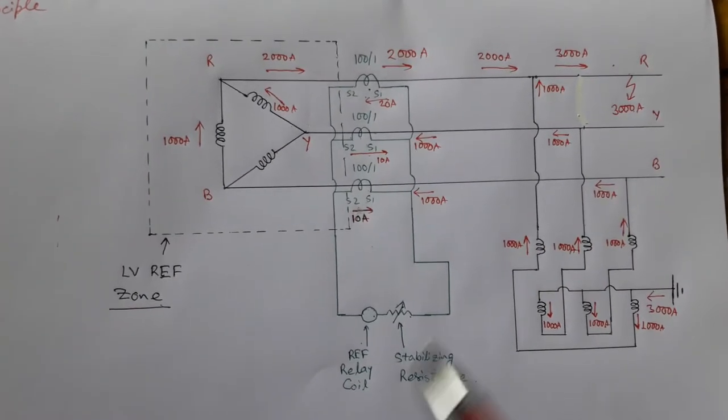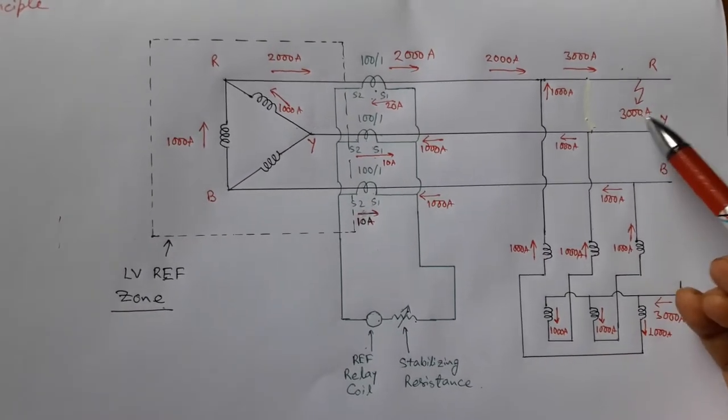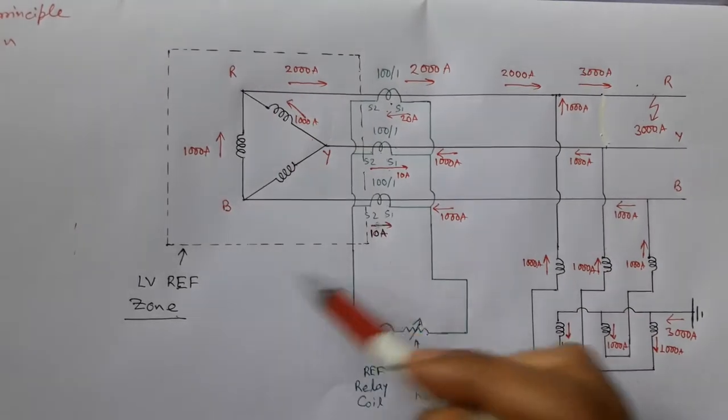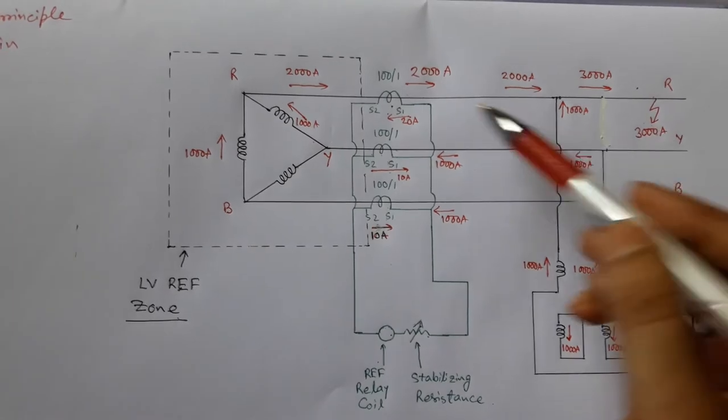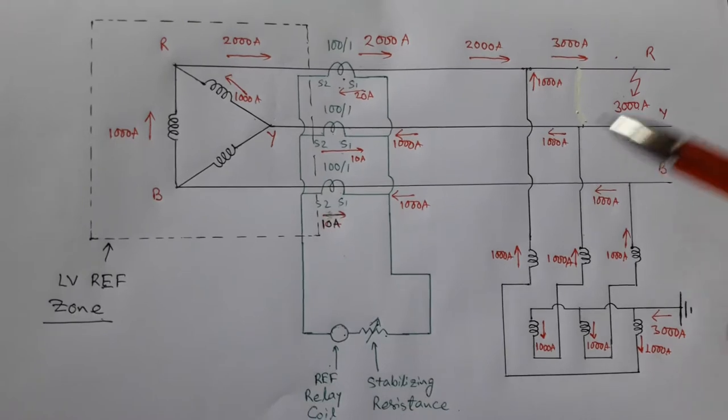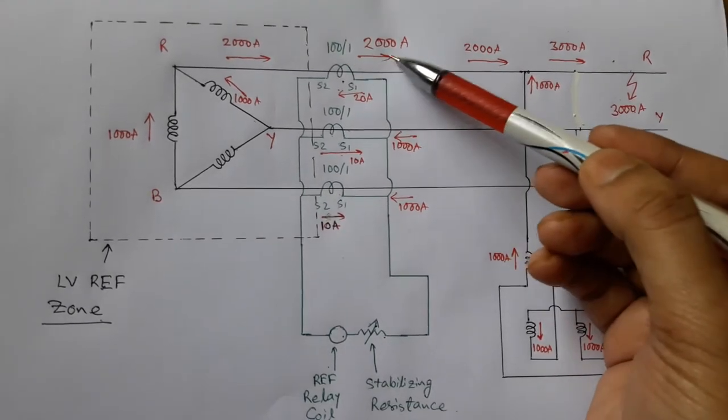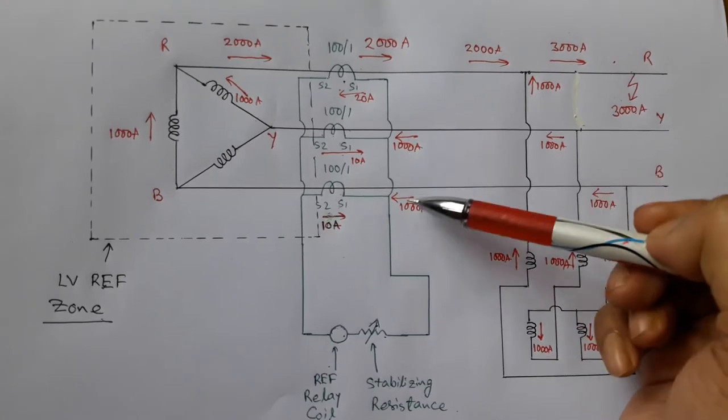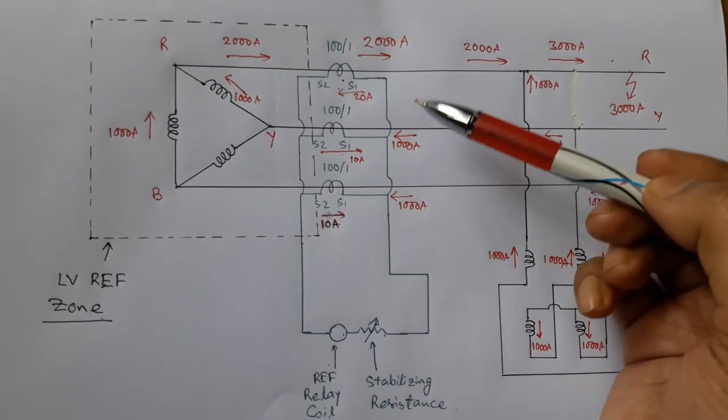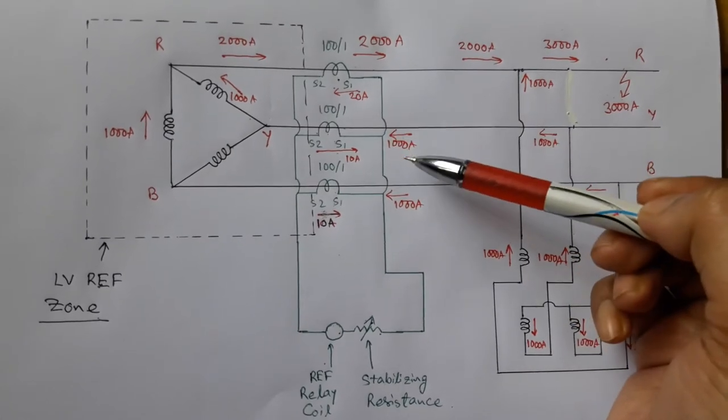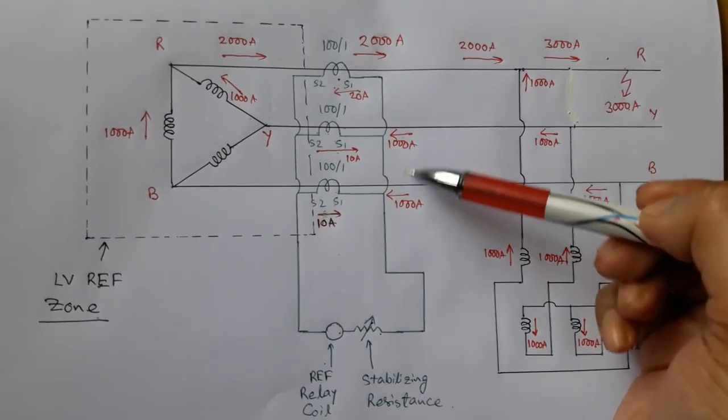In this example, notice that a 3000 ampere fault current has occurred outside this protection zone. This is the current distribution in the primary power system. Notice that current flowing in the red phase is double the current flowing in yellow and blue phases. Also notice that the direction of red phase current is opposite to the direction of current in yellow and blue phases.